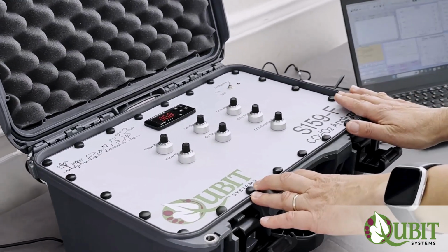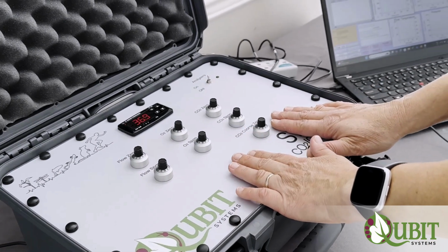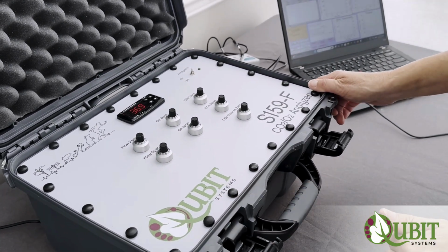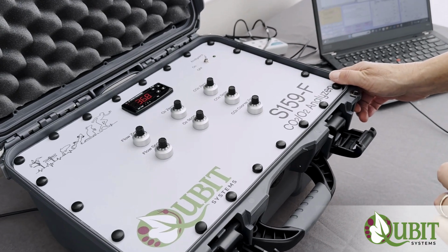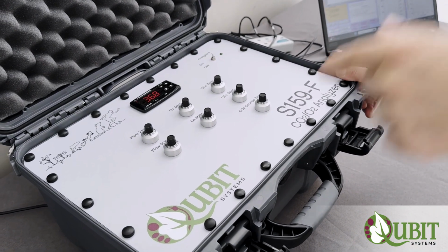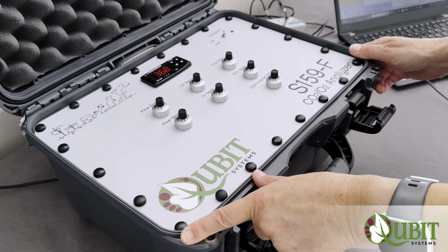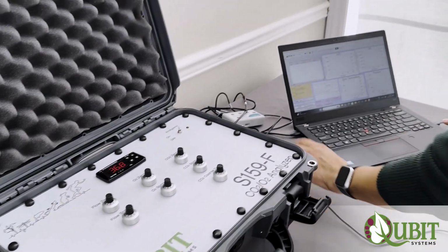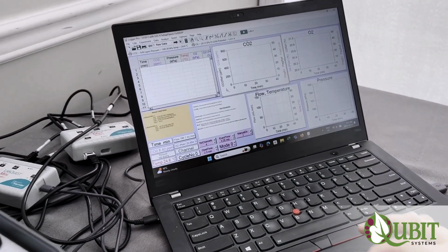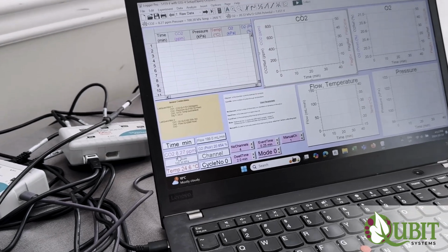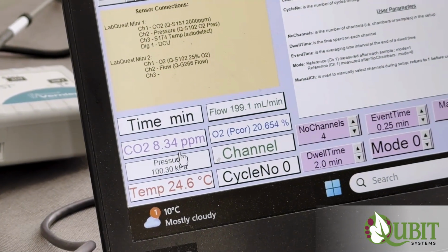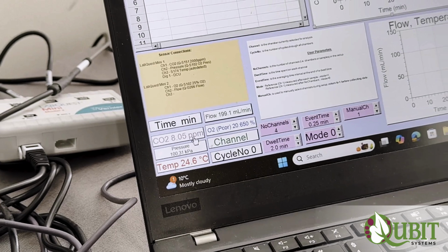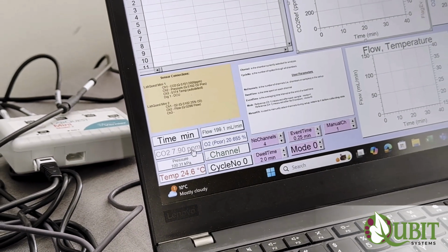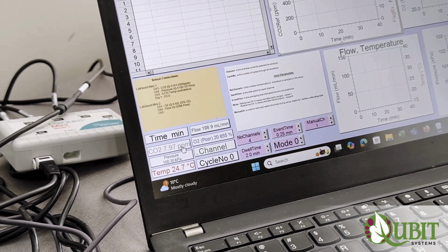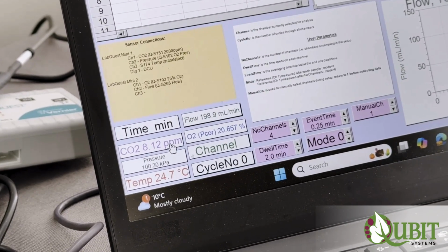The sensors on the S159 analyzer, both CO2 and O2, have a linear response, so all we need is 2 points to calibrate each sensor. We're going to start with the CO2, and we're delivering 0 CO2 right now to that sensor because we're scrubbing just room air through a soda lime column. You can monitor in the software the reading, and you can see here the CO2 is dropping down to 87 parts per million. When this stabilizes, we will wait for a few minutes. When it stabilizes, we will adjust the CO2 zero on the analyzer itself.